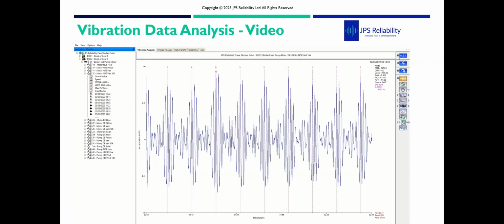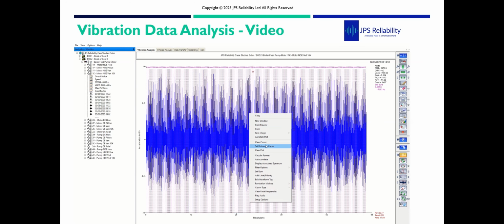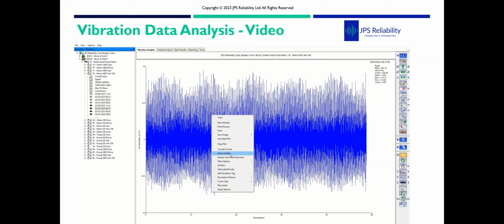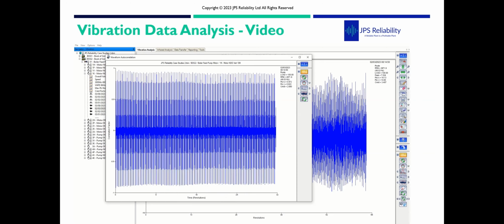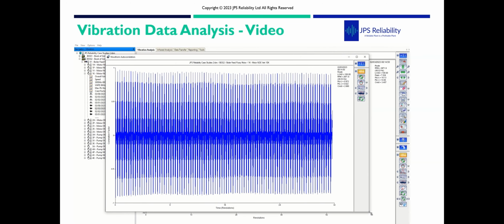Another great thing in this software, if we pull back, is called autocorrelation. So within this time waveform here, if we clear the plot so you can see it again, we can actually autocorrelate. Now what autocorrelate does is it works perfectly only when you have the speed set correctly. We can autocorrelate it and bring out another waveform. Now this shows us what within that data is reoccurring at a period frequency.